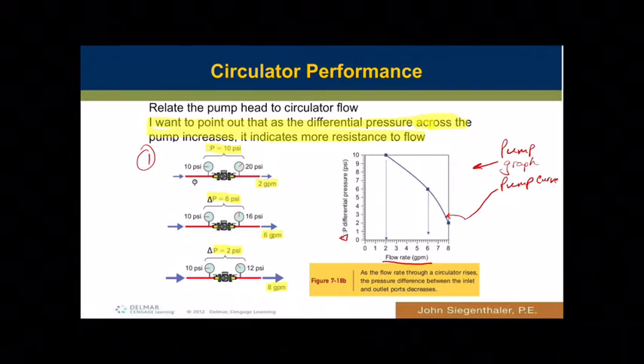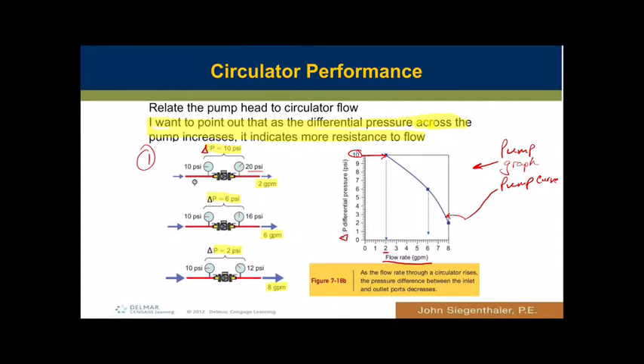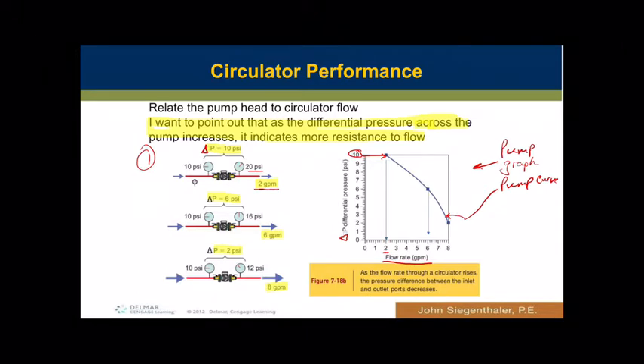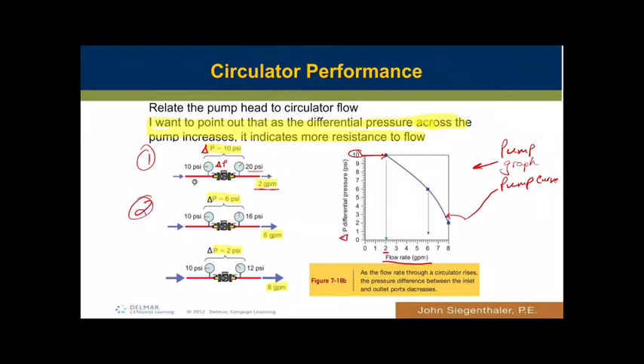If I have 10 PSI going into the inlet side of my pump and I measure 20 PSI coming out of the discharge, that's a delta P of 10 PSI. My pump curve shows 10 PSI, I go over and find where it intersects the curve, and that identifies two gallons a minute. In the field, we're not going to know the GPM until after we measure the differential pressure — it's all about understanding pressures and pressure losses. That would be a point of operation.